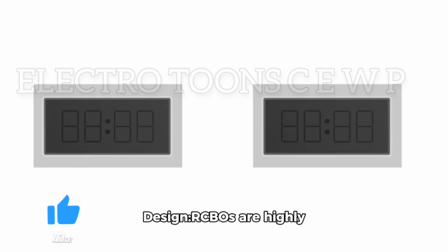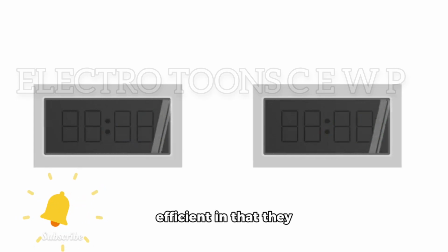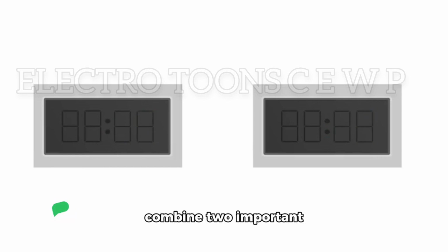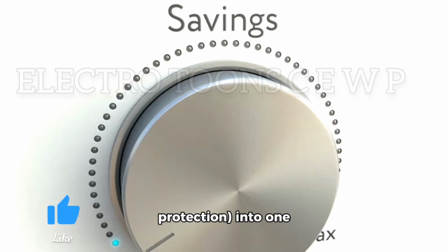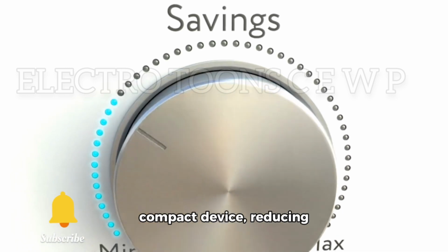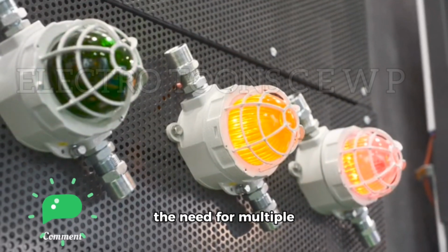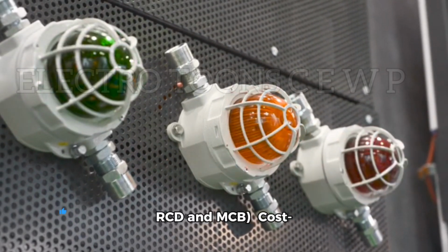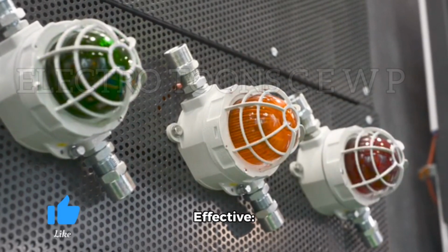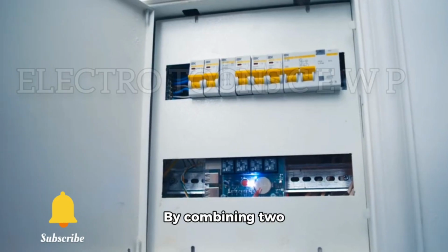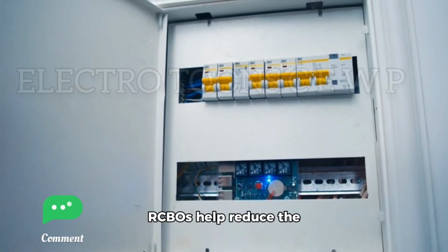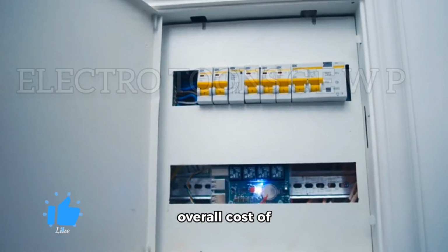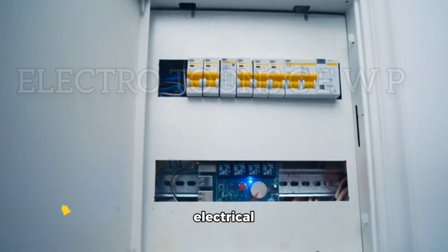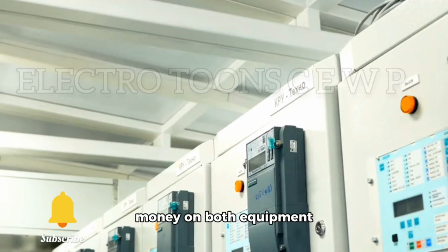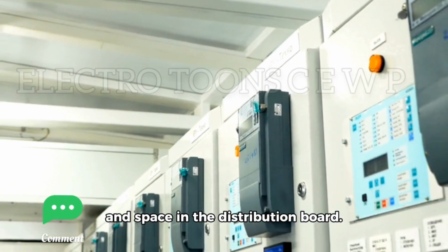Space-saving design: RCBOs are highly efficient in that they combine two important safety functions, earth leakage and overcurrent protection, into one compact device, reducing the need for multiple units, for example, a separate RCD and MCCB. Cost-effective: by combining the protection features, RCBOs help reduce the overall cost of electrical installations, saving money on both equipment and space in the distribution board.